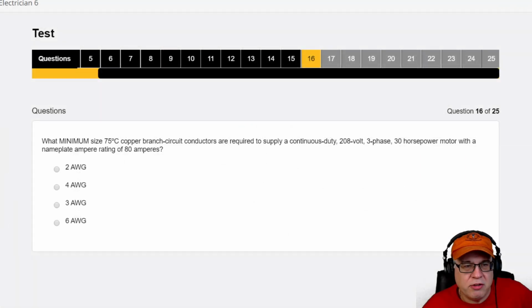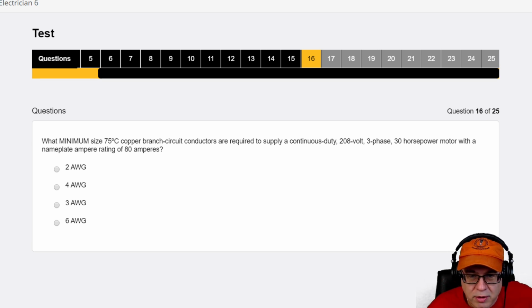Now let's go back to the question. It says 75 degree copper, so we have 75 degree conductor limitations. What else do we need here? Oh, it's continuous duty. So it's a continuous duty motor, which means we have to worry about 430.22, the 125% rule.